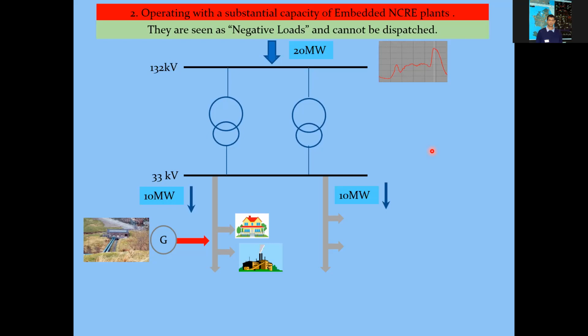But the big problem is the other side. If during off-peak the demand reduces all of a sudden, sometimes the coal power station cannot reduce its output beyond 180. Sometimes you have to switch off coal mills. So during off-peak, our problem is lowering the generation. During night peak, the problem is increasing it. But when you're operating a power system, you keep reserves which can be operated either on the increasing side or the decreasing side. So we always keep a margin in our generators so that we can decrease generation, so that even if the demand is reduced, we have sufficient generating reserves. We call it down regulation, so that we can lower our generation.